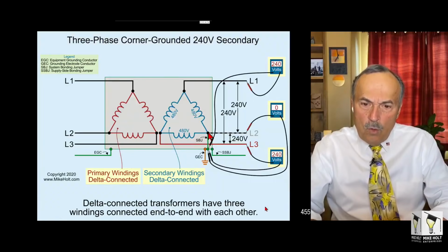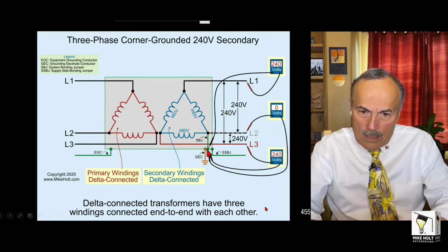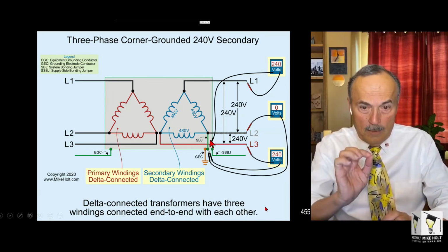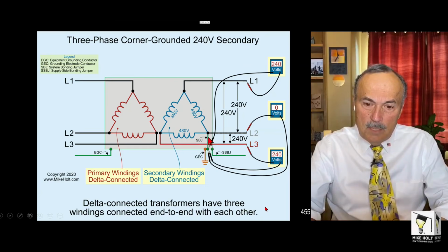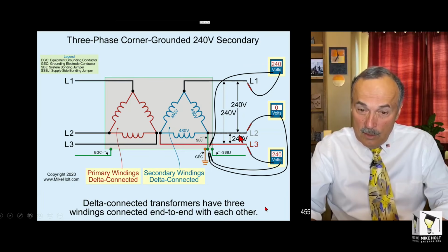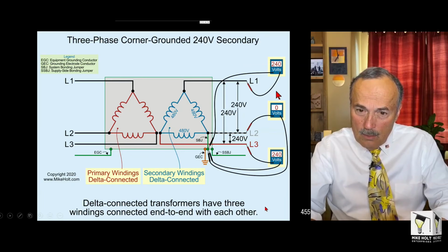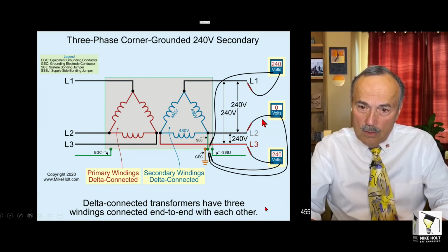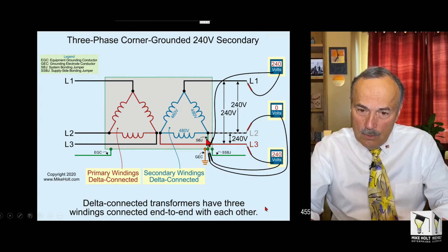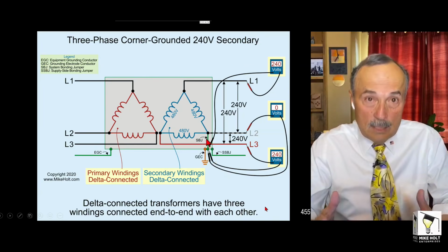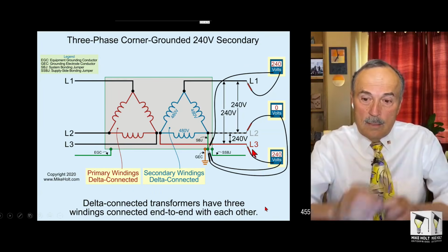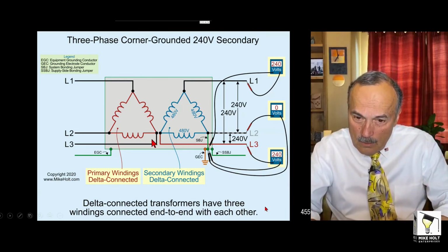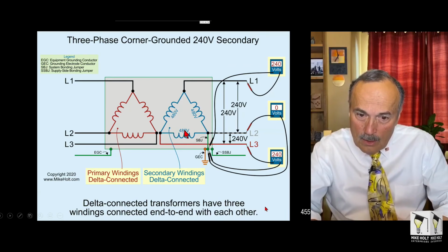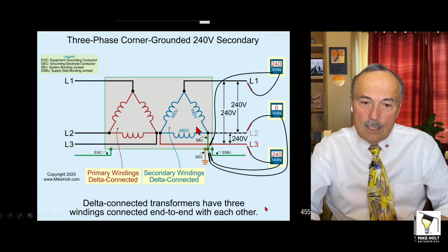And what's the voltage if you're corner grounded? Well, if you're corner grounded, then that's your reference point, period. That means that that's 0 because then you take it to the earth. So your system bonding jumper, and then you have your grounding electrode conductor. And then the voltage between 0, let's see, this is line 1 to 0 is 240. Line 2 to 0, when line 2 is 0, it's 0 because it's the same point. Line 3, which is this winding right here, is gosh, these windings should be 240.